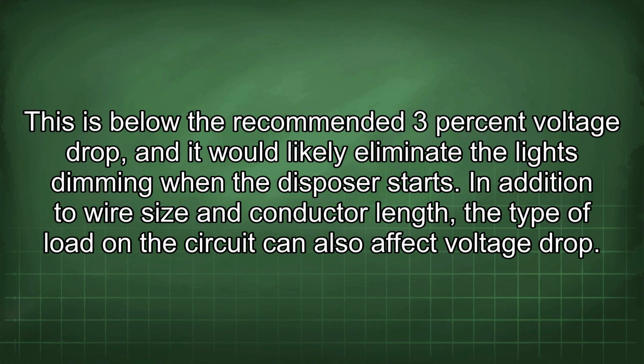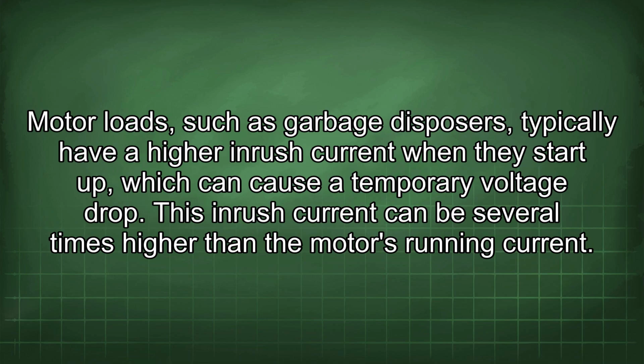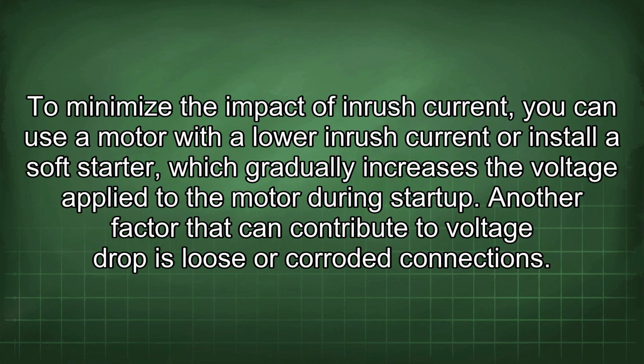when the disposer starts. In addition to wire size and conductor length, the type of load on the circuit can also affect voltage drop. Motor loads, such as garbage disposers, typically have a higher inrush current when they start up, which can cause a temporary voltage drop. This inrush current can be several times higher than the motor's running current. To minimize the impact of inrush current, you can use a motor with a lower inrush current or install a soft starter, which gradually increases the voltage applied to the motor during startup.